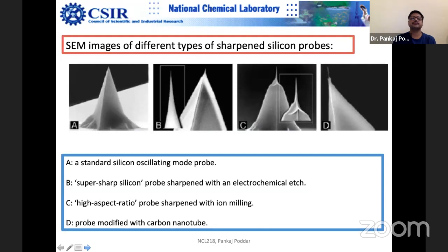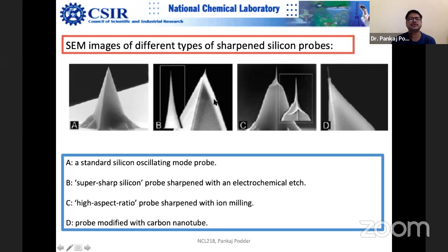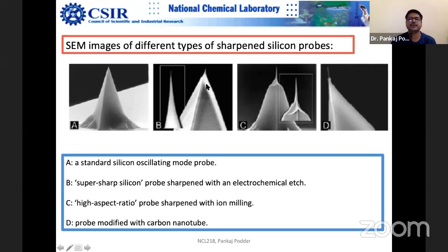It is a good idea to have scanning electron microscopy images of various probes. These are some standard probes: one is a standard silicon oscillating-mode probe used for tapping mode imaging, and another is a super-sharp silicon probe sharpened with an electrochemical etch, which can be done in the laboratory. You can design an electrochemical cell and carefully etch a tip to produce a sharper probe. After modification, you should characterize it and take SEM pictures of the dimensions.